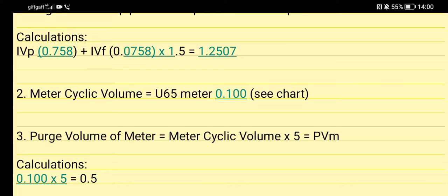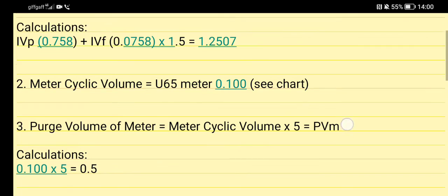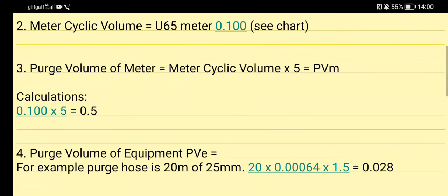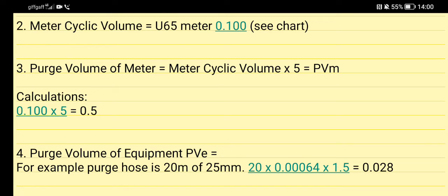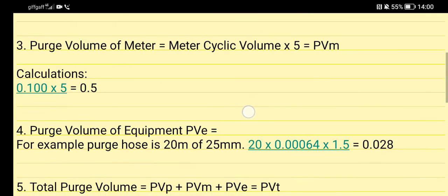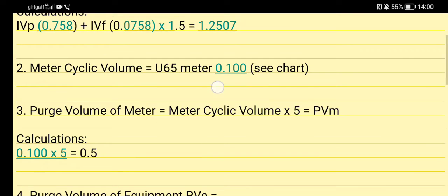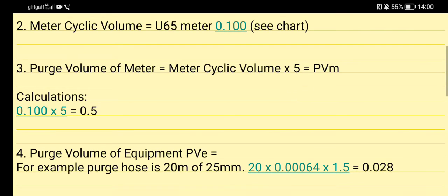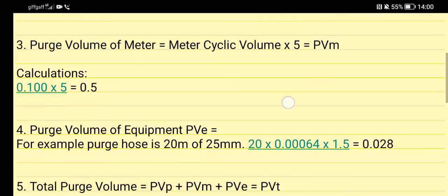When you get to your meter cyclic volume, you've got your U65 meter. You have to look in your book to find this 0.100 - you should see in a chart. You bring that down to stage 3 and then you get your purge volume of meter. Your meter cyclic volume times 5, so that's P to give you your PVM. That's 0.100 that we got from here, and we times that by 5, and that gives us 0.5.